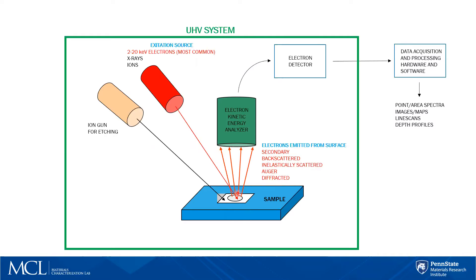Some fraction of all of them are drawn into a kinetic energy analyzer that measures the kinetic energy distribution of all this stuff coming off the surface. The output from the analyzer is fed into an electron detector, and the detector output is fed into data acquisition and processing hardware and software, which generates the typical Auger data that we analyze. If we want to study subsurface atoms, we need a way of etching material away, so most Auger systems also include an extra ion gun for etching the sample surface and allowing study of things subsurface.